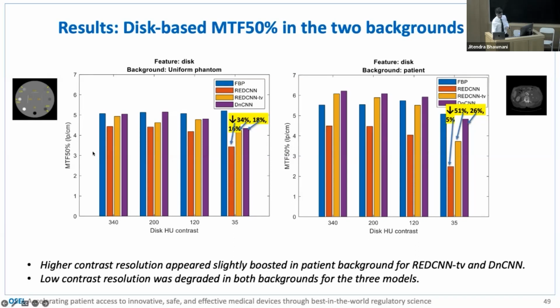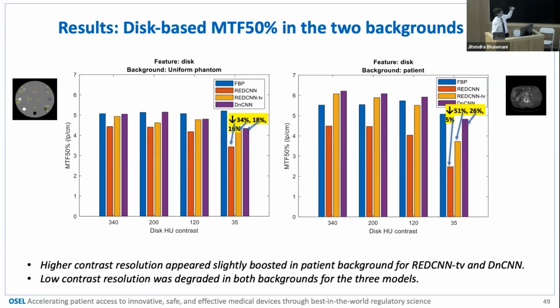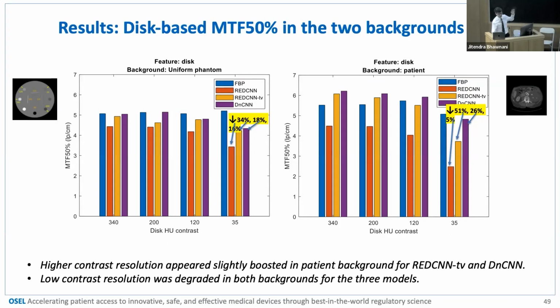And in all cases, actually, the filter back projection has the best. This is the MTF 50%, so half of the MTF. The filter back projection actually has the same performance in all the contrast, and it's actually on the top. And the denoising has a similar performance, except for the lowest contrast. At the lowest contrast, the performance of the denoiser goes down, which we understand, but that's very problematic because it's usually low contrast many times. So in the anatomical phantom, these disks have a similar trend, but there's really strong fall in performance, like more than 50% fall for some of these. This other one, the DnCNN, actually did a better job.